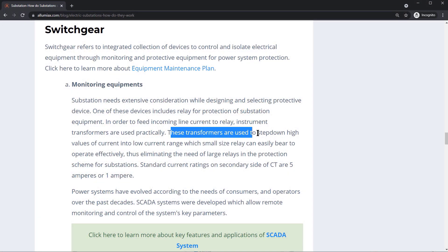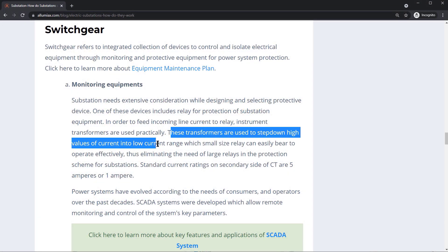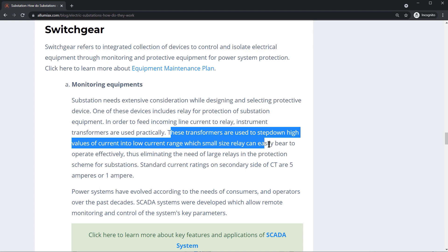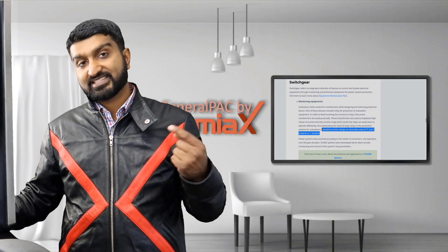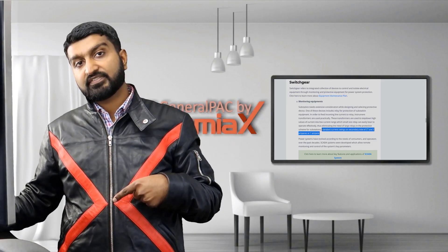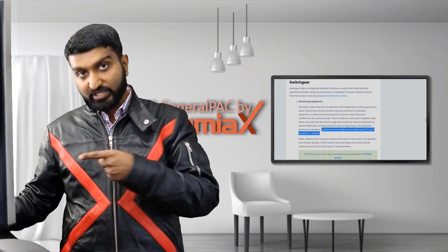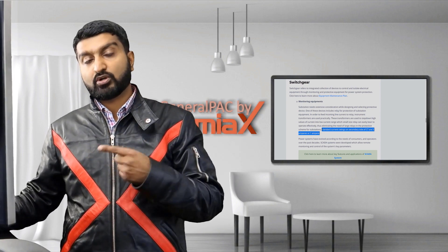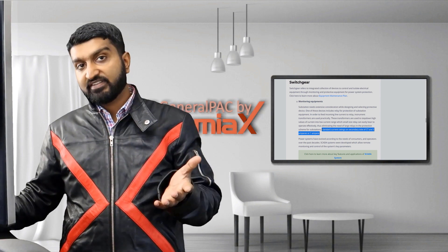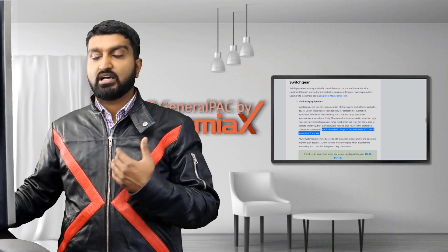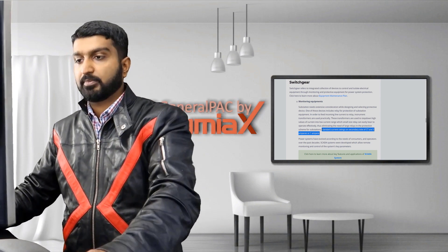Current transformers are used to step down high values of current into low current ranges, which small-size relays can easily bear to operate. Normally, the current on the secondary side of the CT going into the relay, meter, or other devices is either 5A-rated or 1A-rated, depending on the application.